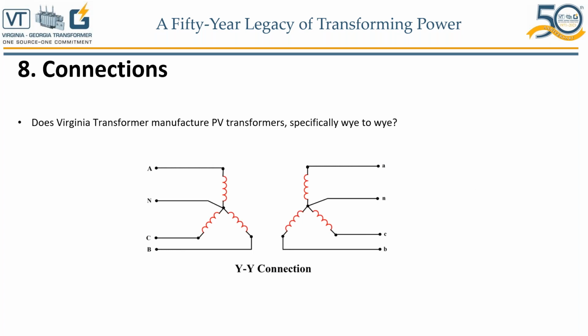Going into the next one. Does Virginia Transformer manufacture PV transformers, specifically Y to Y? I'm not good with acronyms, but I'm going to have to assume the PV transformer stands for photovoltaic step-up transformer. If that is the case, because I'm sure the submitter of this question is not asking simply, can we do a YY transformer? Because the answer to that is very simple: yes, of course we can do YY, we can do Y delta, delta Y, whatever you want. But I'm going to have to once again assume that we're talking about photovoltaic step-up transformers. If that's the case, then no, the photovoltaic transformer's high side will be delta and the low side will be split Y. So it's going to have two Ys on the low side with a high side delta.